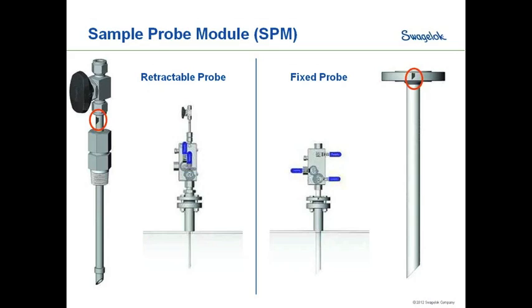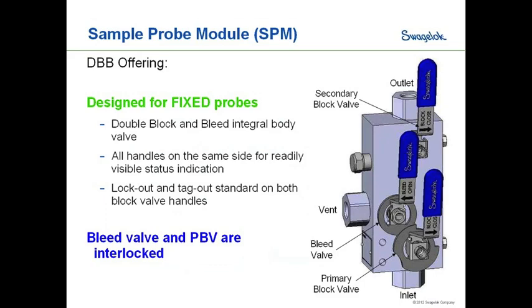For the fixed probe, there's a bleed valve and a secondary block valve interlocked with the primary block valve. In the operating position, the sample is coming out and you cannot open the bleed valve — the cam prevents it. By rotating the primary block valve off, the bleed valve is released. They're interlocked so you can't turn the bleed valve on while the main valve is on, and you have to turn the bleed valve off before turning the main valve back on — a safety-conscious design.